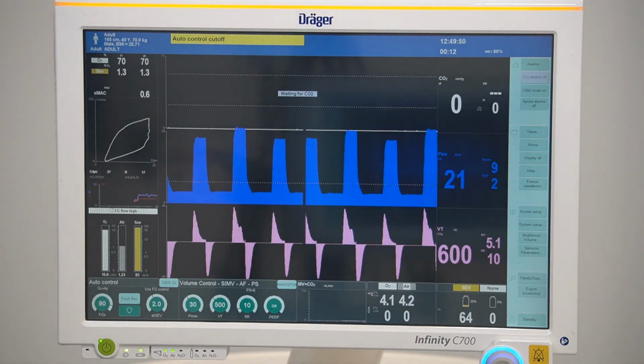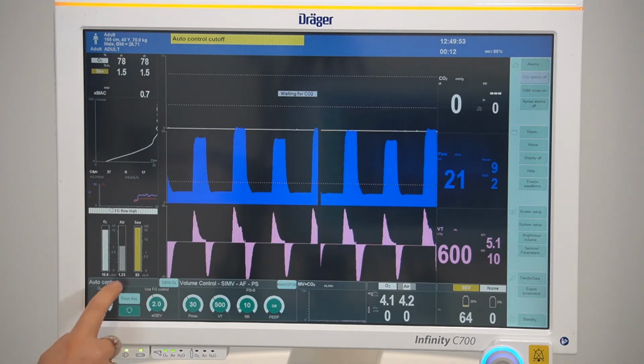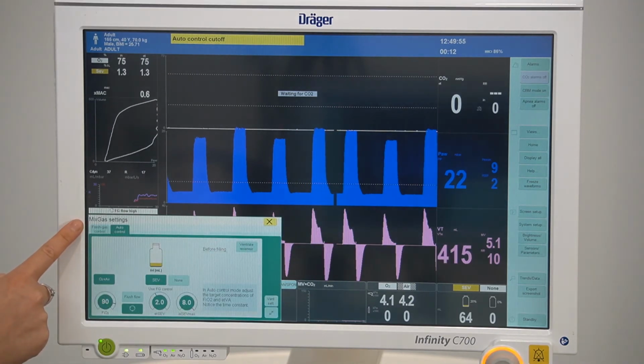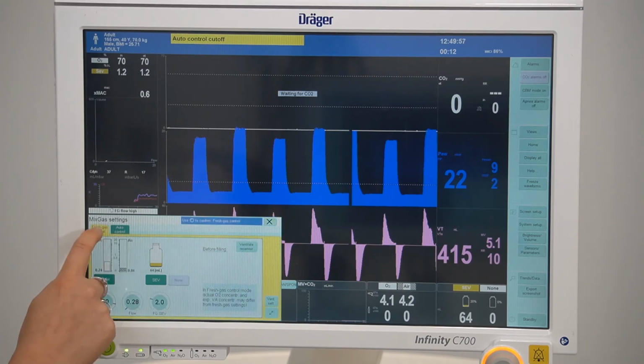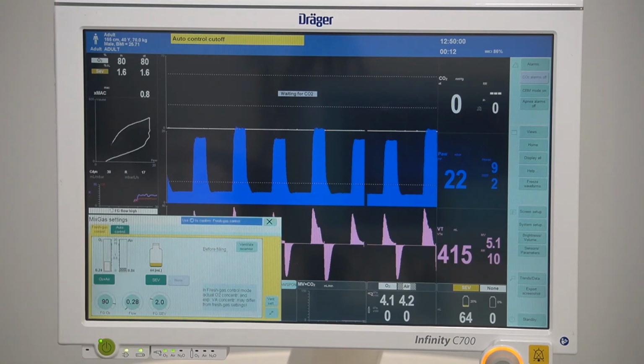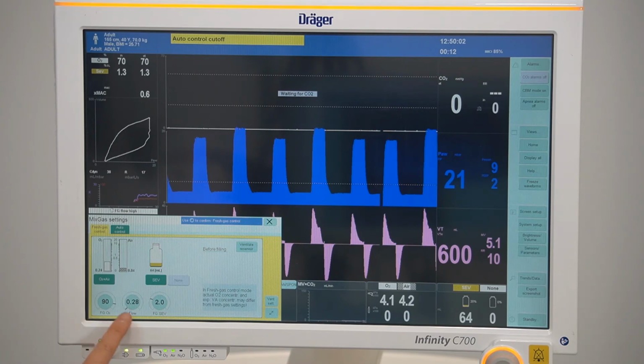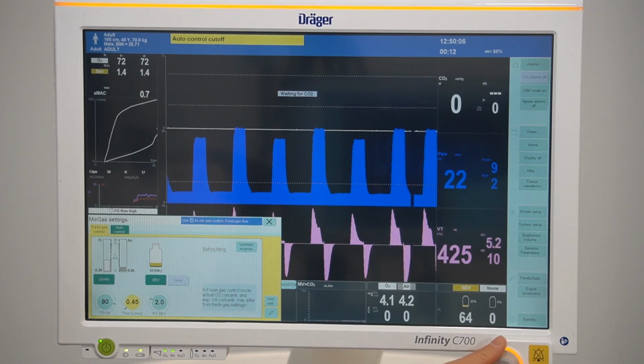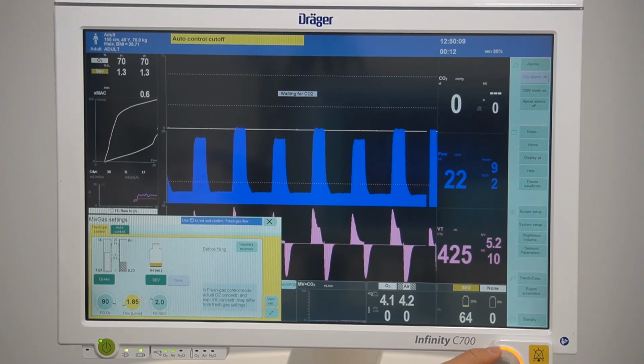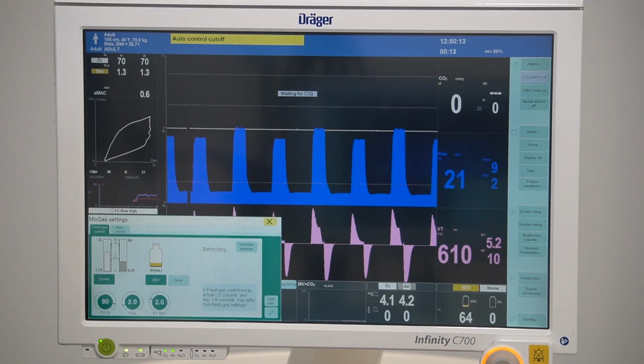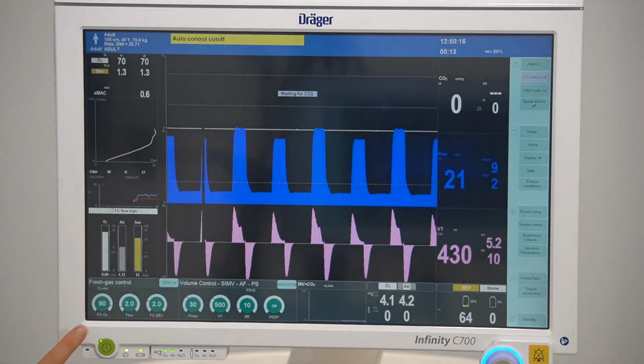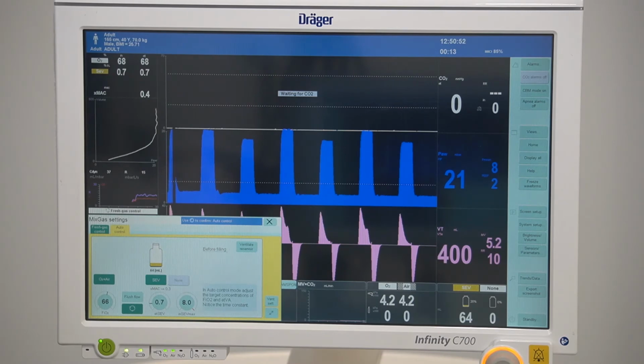The user should switch to fresh gas control by opening up the mixed gas settings dialog window, selecting fresh gas control, and verifying your fresh gas settings and your volatile settings. And confirming. Once the user has checked the device for a leak, you can return to auto control.